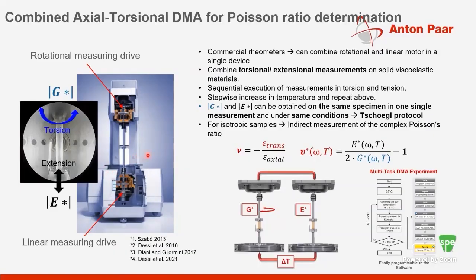Now, if you take a look at a critical review paper which was written by Tschoegl, I think back in the early 2000s, I'm talking about the Poisson ratio determination here. This is the unique application I'm talking about, where one of the things mentioned in that critical review paper was the need of a device which can actually do measurements on the same sample in the same environmental conditions, so that the boundary conditions and everything are the same. So Tschoegl dreamt of a device where this could be done, if it was even possible to do such measurements. And recently we have developed this, where you can set up a multitask experiment and measure G and E at the same temperature on the same sample without changing it. And for an isotropic sample in the infinitesimally small strain limit, Poisson ratio can be defined as shown here.